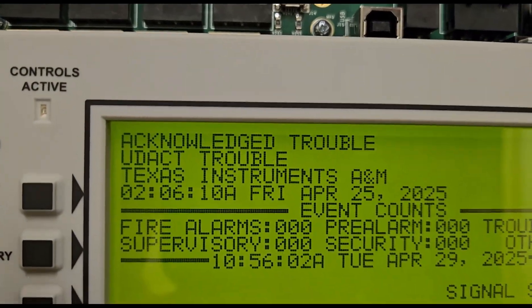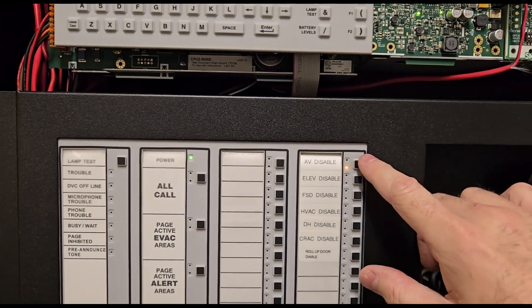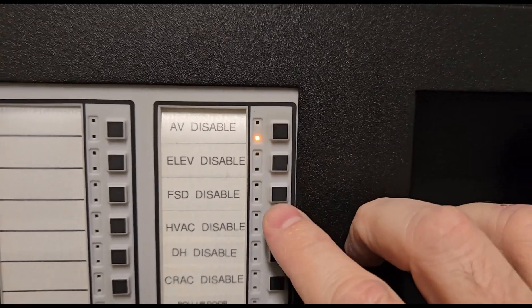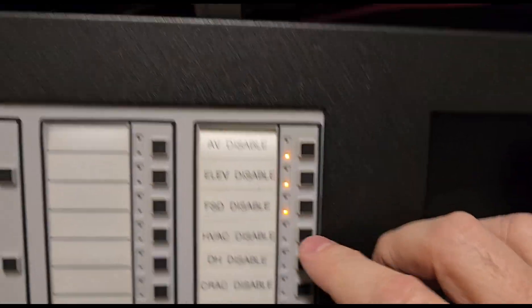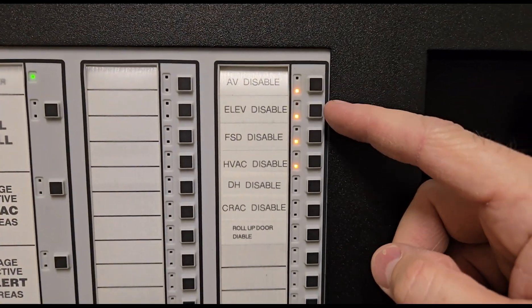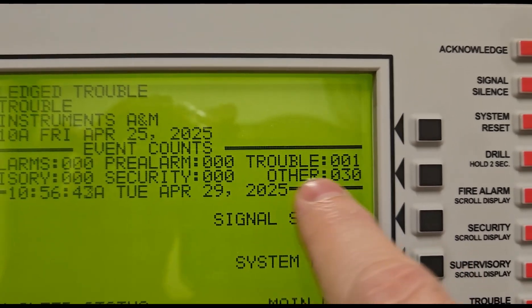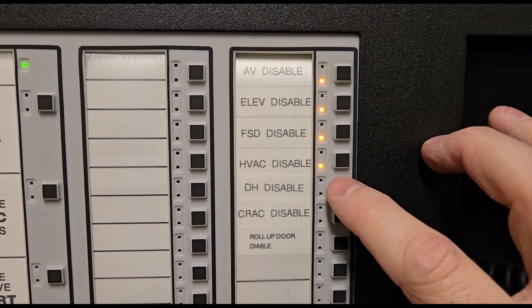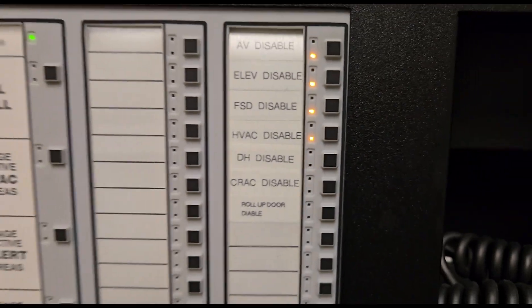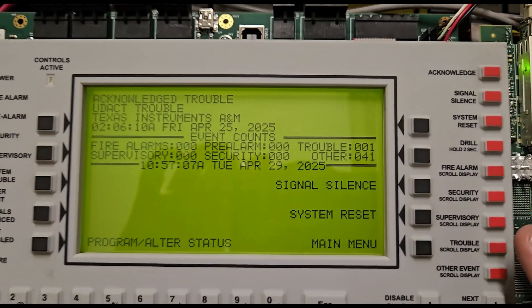If you hit the other button you'll see it shows that trouble and it'll say logic zone number one — the logic zone corresponds to this disable button. Now we're going to do the rest of them: elevator disable, FSD disable, HVAC disable — you can see the lights coming up as they populate, letting us know which ones are disabled. After four buttons we have 30 other signals. Then we do door holder disable, CRAC disable, and roll-up door disable.